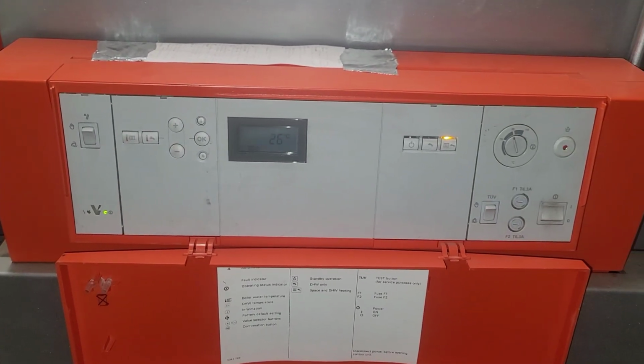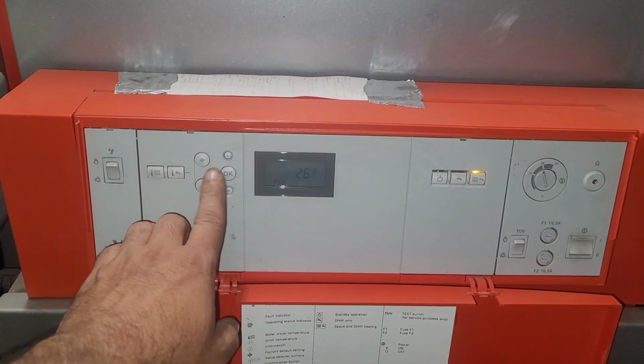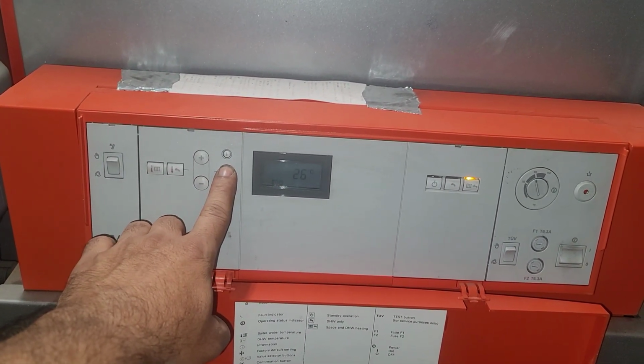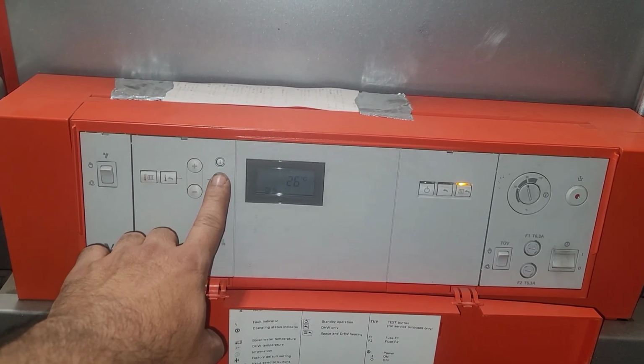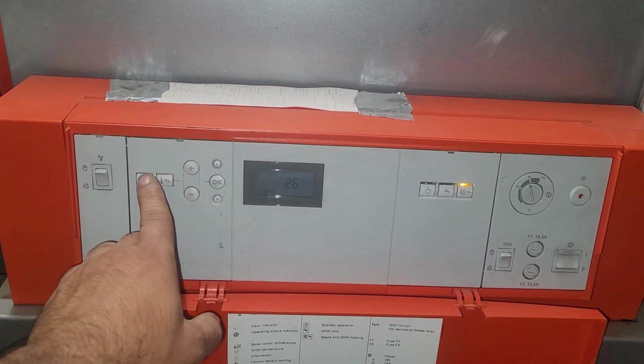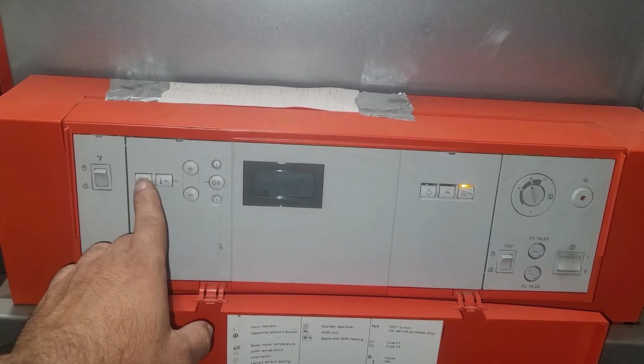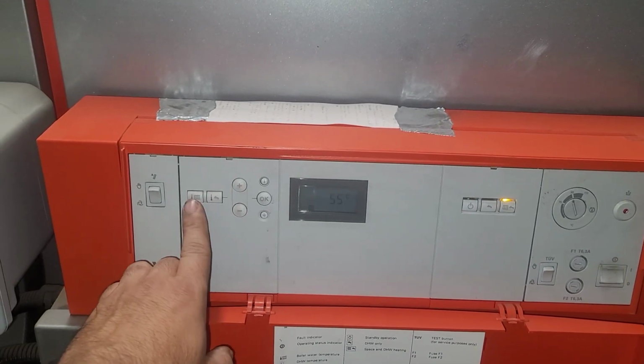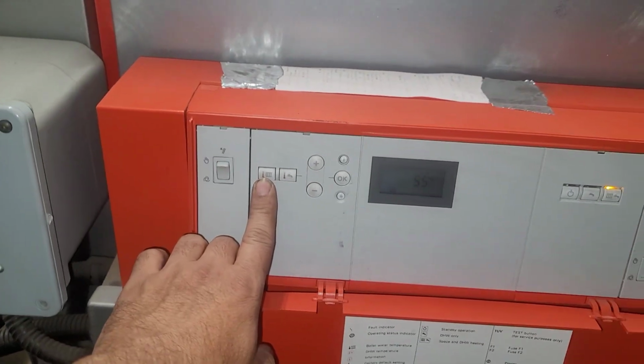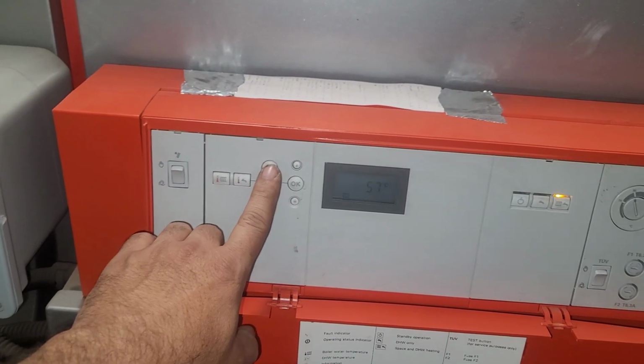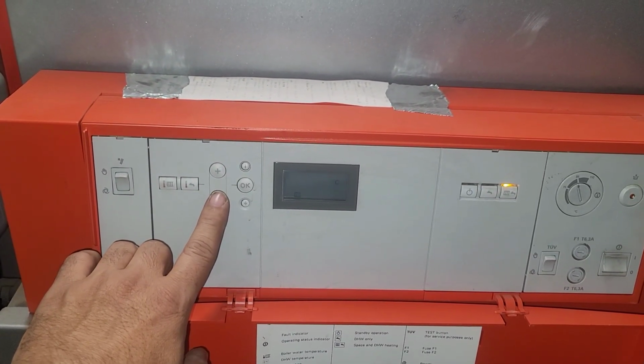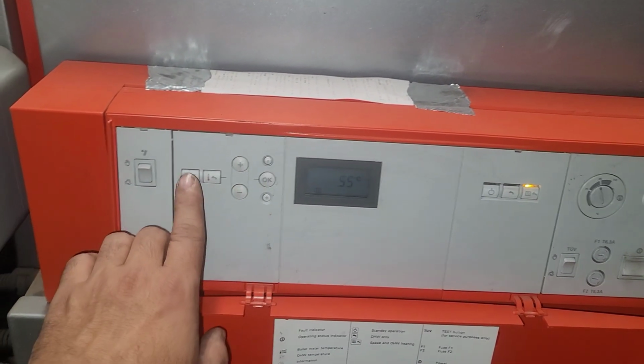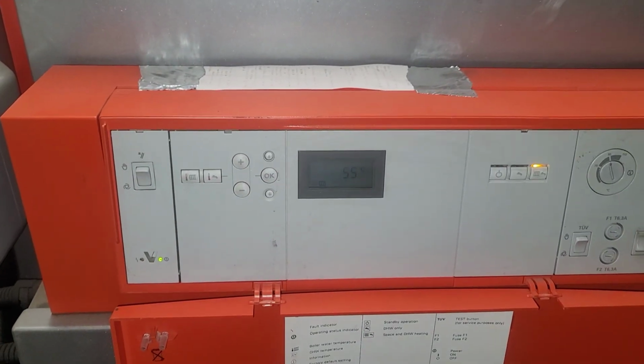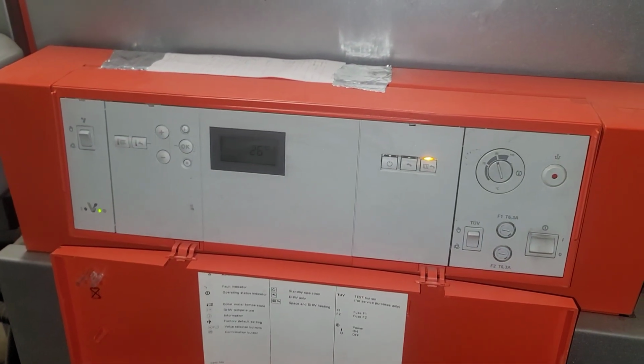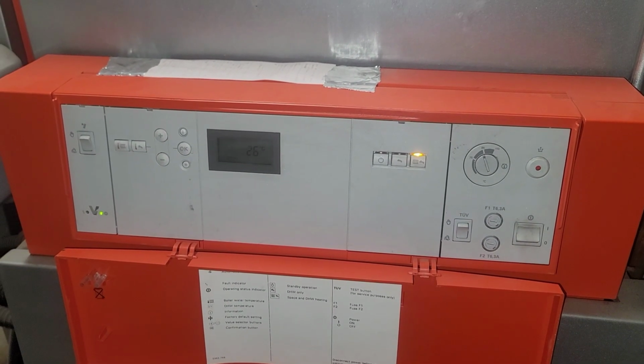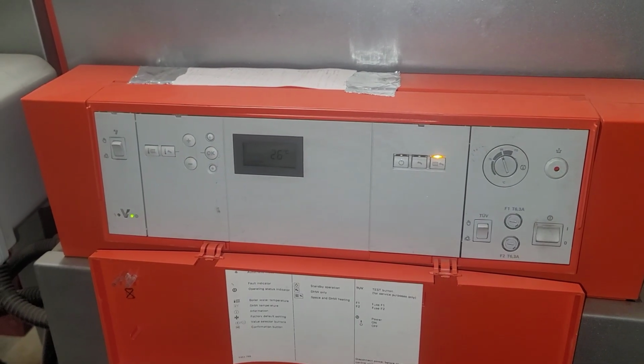Okay, so it has its own delay. Here we have to put it onto the space heating, and plus and minus we can increase or decrease. So right now I'm not touching it. 55 degrees Celsius is a preset value. Okay, so it has its own delay and it will fire up soon.